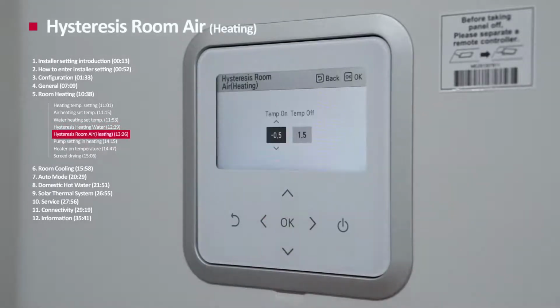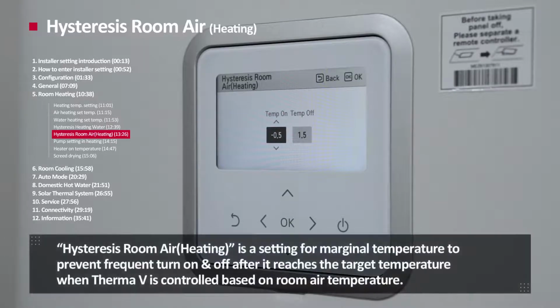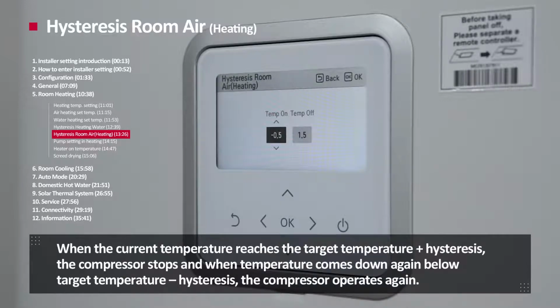Hysteresis room air heating. Hysteresis room air heating is a setting for marginal temperature to prevent frequent turn on and off after it reaches the target temperature when Therma V is controlled based on the air temperature. When the current temperature reaches the target temperature plus heat statuses, the compressor stops. And when temperature comes down again below target temperature minus heat statuses, the compressor operates again.